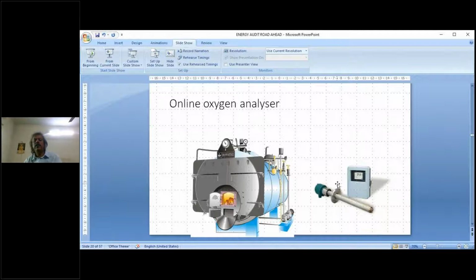Today, as we talk about developments in technology for efficiency, we need to talk about developments in the instrumentation side. A lot of portable instruments have come. This is an oxygen analyzer. We have, of course, a portable kit. This is an online oxygen analyzer. Because the operator who is operating the boiler needs to know how we can maintain high efficiency. He should know that using too much air means wastage is too much, so we need to control.